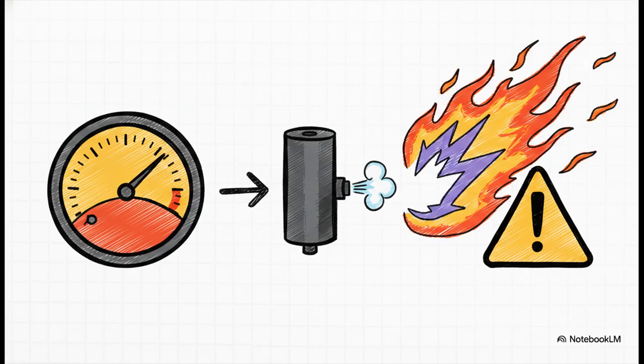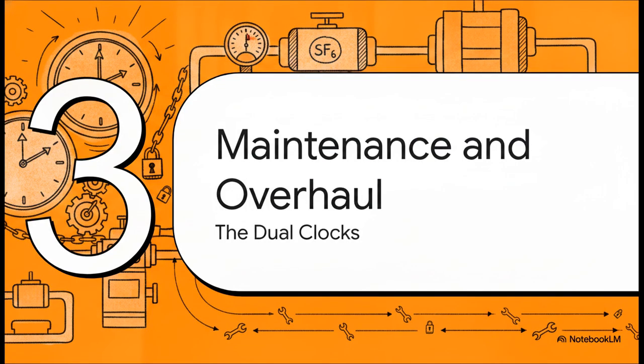Below 2.0 bar, the pole just cannot guarantee fault interruption anymore. If an arc strikes at, say, 1.9 bar, the puffer cylinder simply doesn't have the SF6 density required to blow the arc out. That means a localized fault could easily escalate into a catastrophic switchboard fire. And nobody wants that.